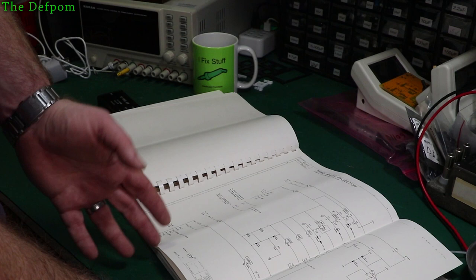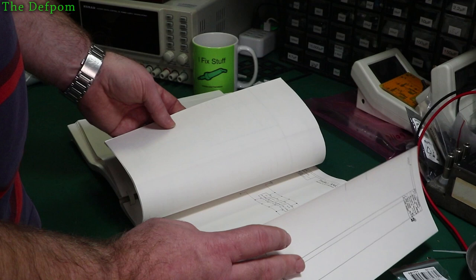This is why I like having a physical manual — sometimes it's just a bit hard to read on the screen and you're relying on the quality of the scan. Sometimes you can get really good electronic manuals, but sometimes they're not so great. I've actually done no repairs on the DATRONs using the electronic manuals, but I still like to get a physical copy. The 1062 is basically the 1061A with the options by default — that's what I saw mentioned on the EEVblog anyway.